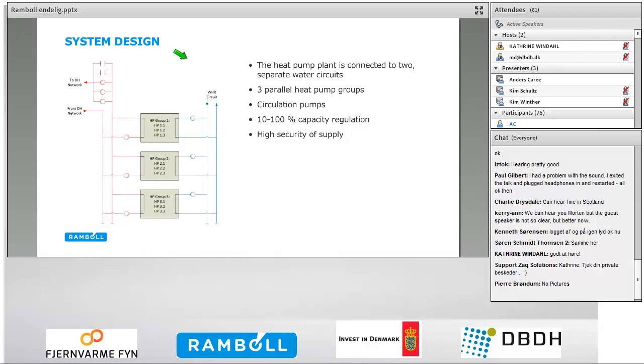On the left-hand side, the heat pumps will then deliver the recovered waste heat at higher temperatures to Fjernvarme Fyn's district heating network. The heat pump system itself consists of 3 parallel groups. The 3 groups are almost identical, except that one of the groups is supplied with variable speed drives, which allows for greater capacity control. And meanwhile, the other 2 groups consist of fixed speed machines that will operate with a slightly higher efficiency during full load conditions, which we expect to occur most of the time.